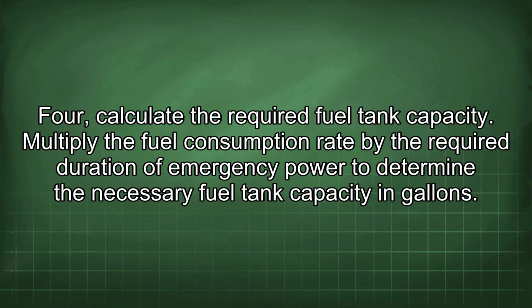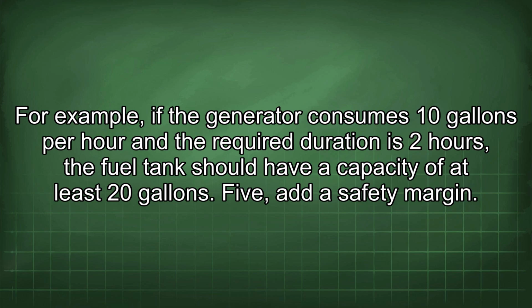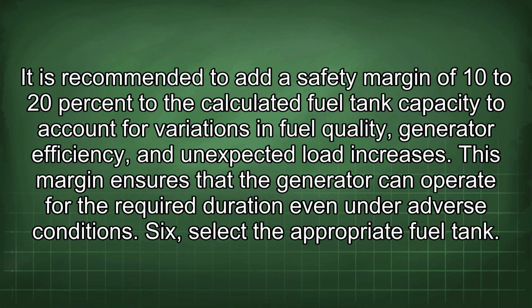4. Calculate the required fuel tank capacity. Multiply the fuel consumption rate by the required duration of emergency power to determine the necessary fuel tank capacity in gallons. For example, if the generator consumes 10 gallons per hour and the required duration is 2 hours, the fuel tank should have a capacity of at least 20 gallons. 5. Add a safety margin. It is recommended to add a safety margin of 10 to 20% to the calculated fuel tank capacity to account for variations in fuel quality, generator efficiency, and unexpected load increases. This margin ensures that the generator can operate for the required duration even under adverse conditions.